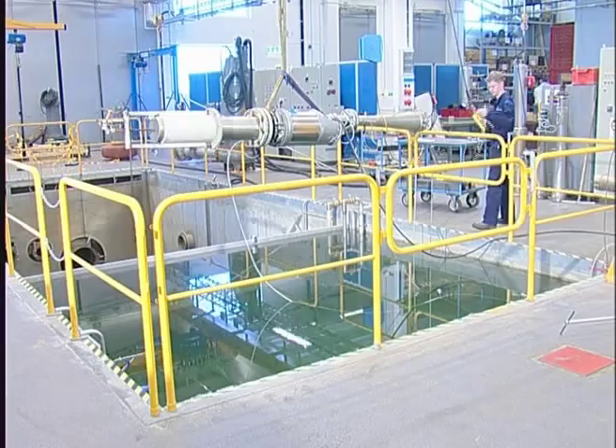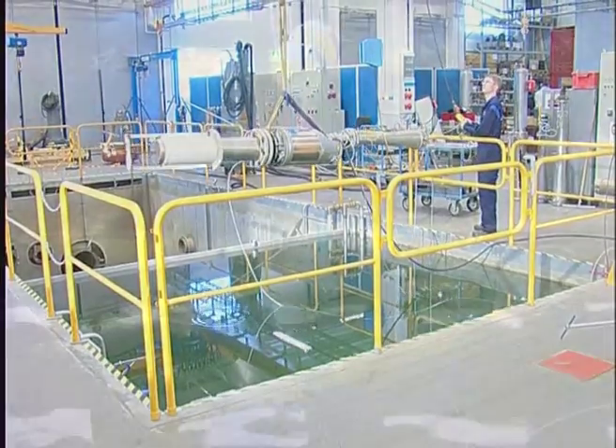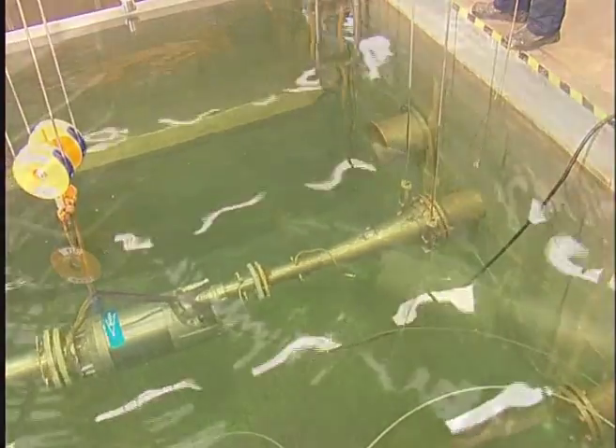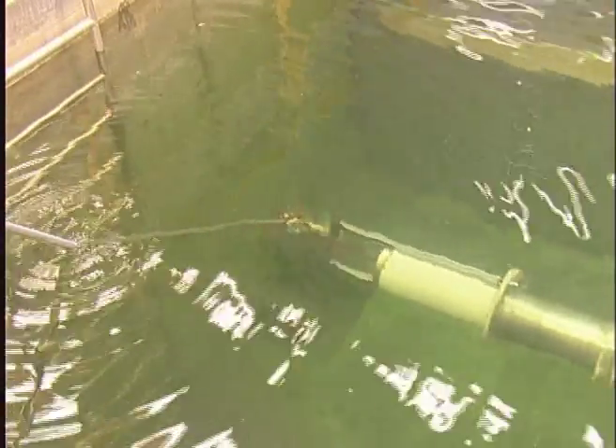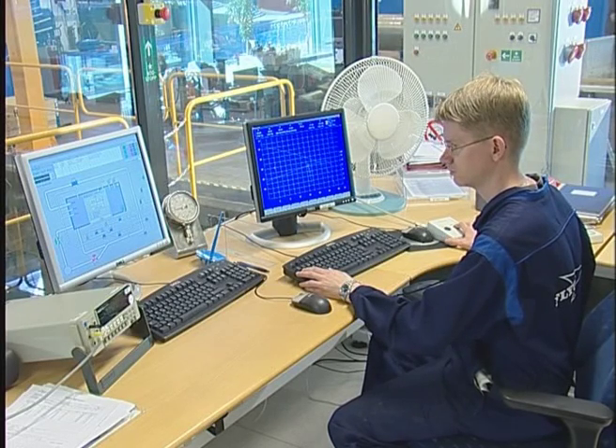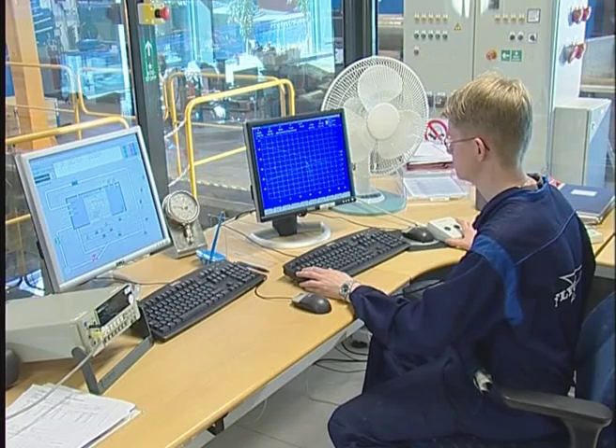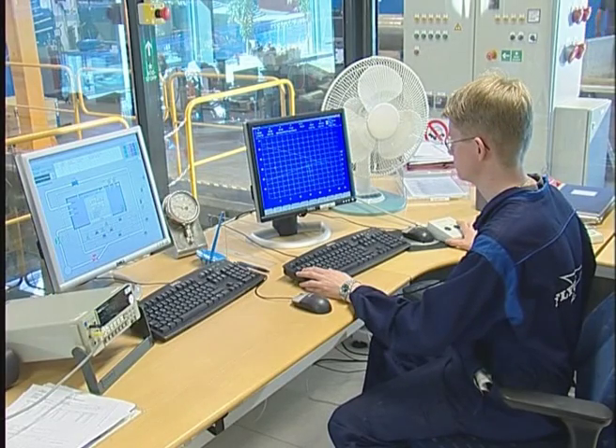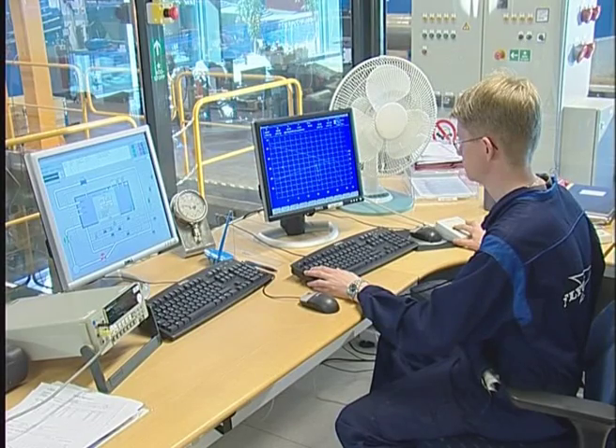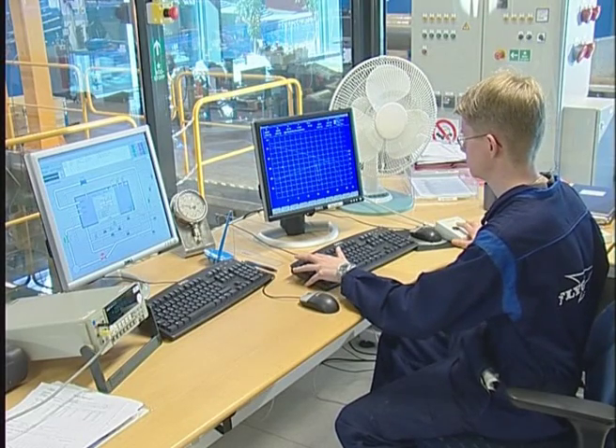The pump is lowered into the basin. The inlet valve is being adjusted for each test run. The pump is started from the control room. Head, flow, and power are being monitored and measured during the test. The water temperature and the atmospheric pressure are also registered.